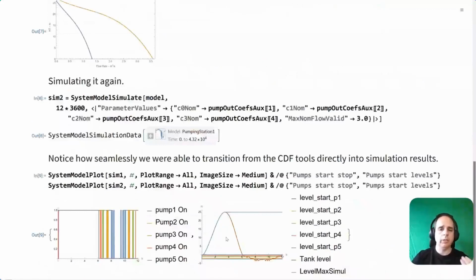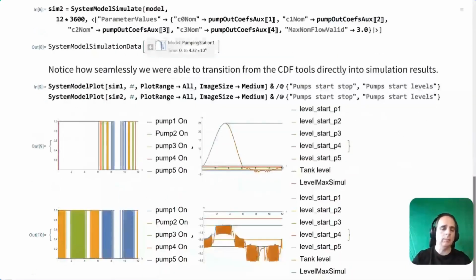These plots we had already seen before. And now it is extracting the information from the simulation, and we'll see in a couple of seconds the new one. Yes. And so with these bigger pumps, we can see that we no longer jump to 25 meters of level around 3 o'clock. I don't know, in the morning, in the afternoon, it doesn't matter.